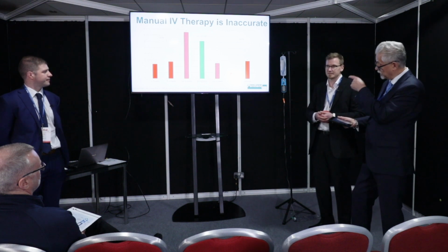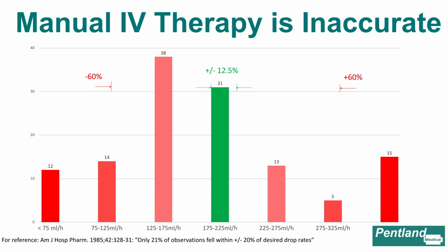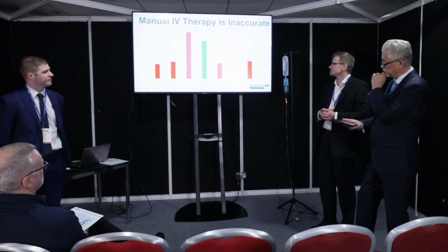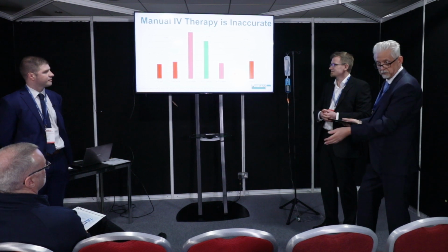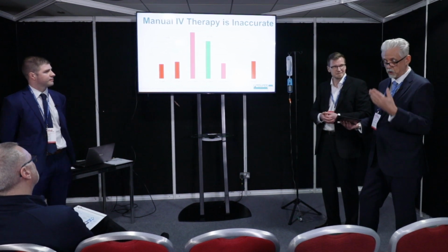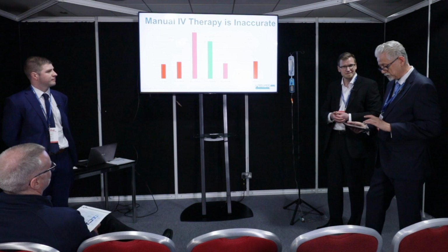And you can see there in the green bar graph that only 31 out of 129 nurses could reach 12.5% accuracy. Now, the Monidrop device has a better accuracy at plus minus 11%. But look at those extremes. I mean, 20 to 25% of nurses under-infused or over-infused the patient, so caused basically danger to the patient's condition.